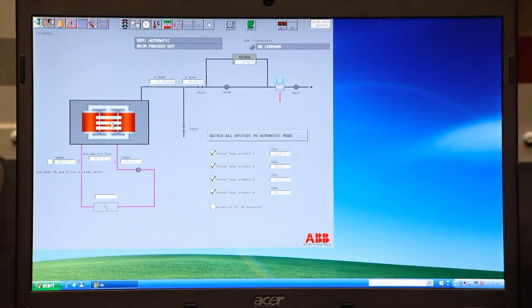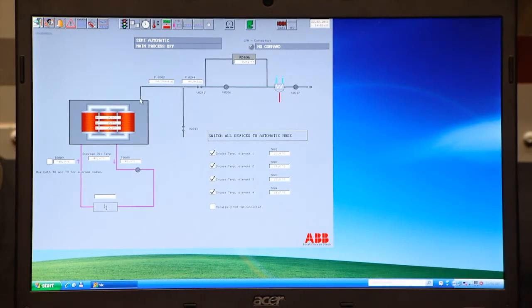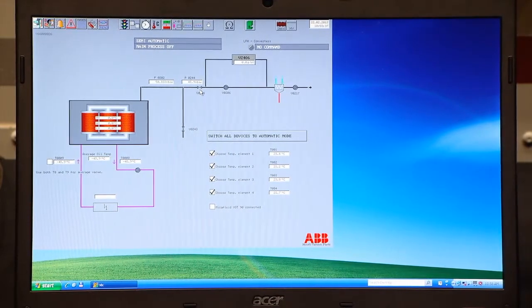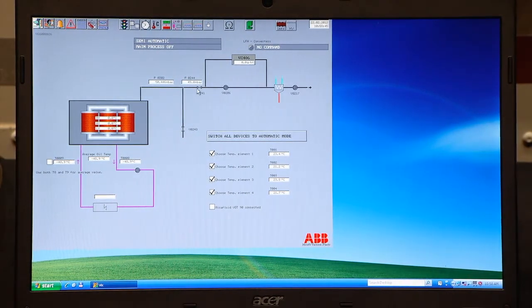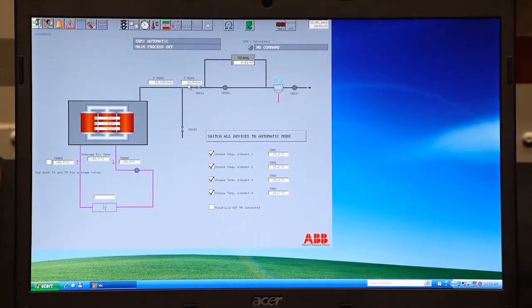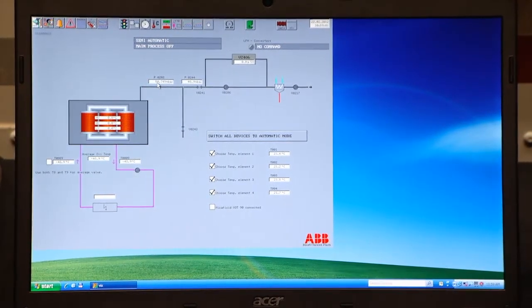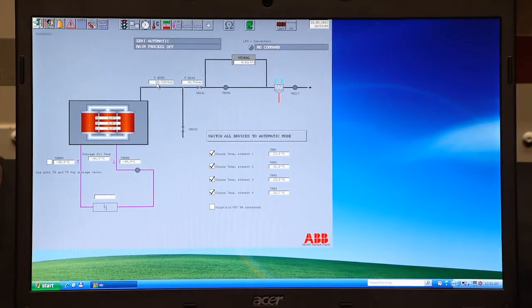These are actually the calculated temperatures and not the temperature sensors which we have installed. You have a schematic picture of the vacuum line to the vacuum regulation valve mounted on top of the transformer. You have the aeration valve for letting the dry air inlet to the system, and these two are automatically controlling the pressure level inside the transformer. We now have the coarse pressure in the transformer at 49 millibar, and since we are at this pressure range, the Pirani measurement sensor is showing a little bit different value.